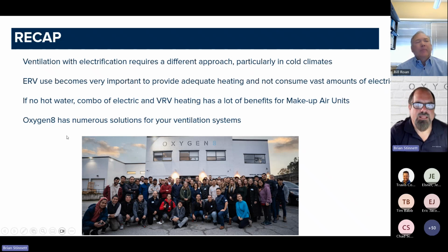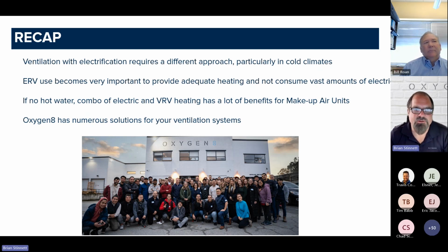Just as a recap, Oxygen8 makes a number of different ventilation units, as you've seen. And when you're looking at doing ventilation and taking electrification into the mix, it requires a different approach than what you've typically used in the past. And ERV, as you've seen, can become very important when designing ventilation systems with electrification, because I can get a massive amount of preheat. I can recover, like I said, roughly 70% of that sensible temperature from the exhaust air and preheat that incoming outside air. And so just keep in mind that Oxygen8 has a number of different solutions for ventilation systems, as we've talked about today.